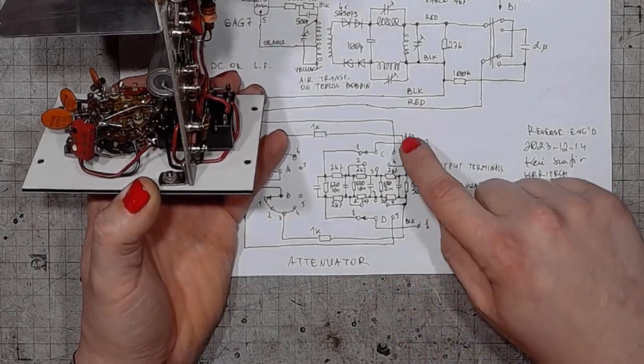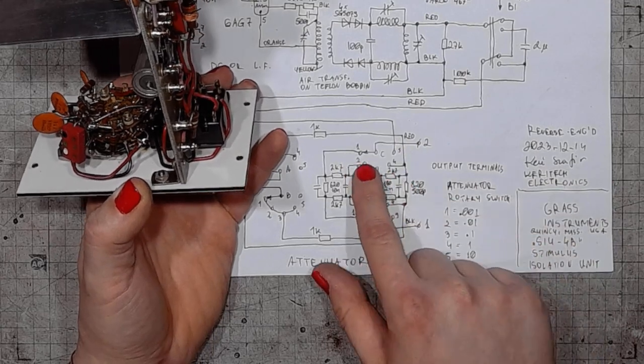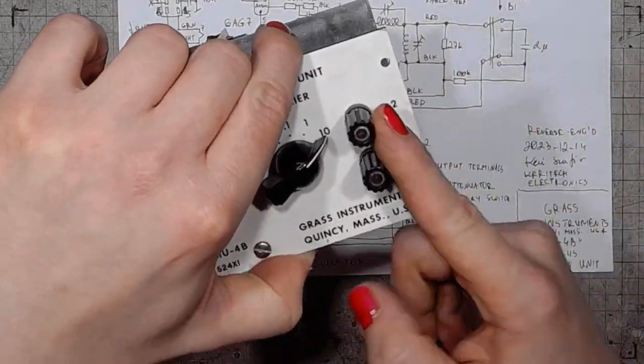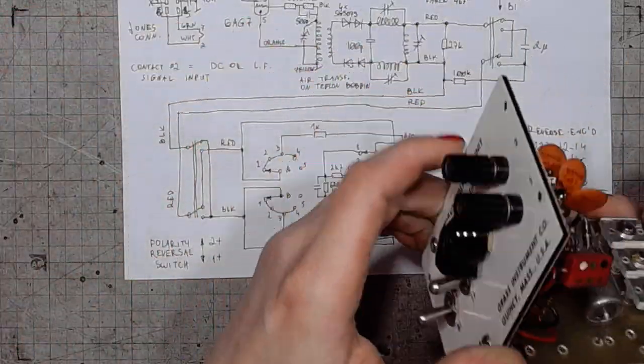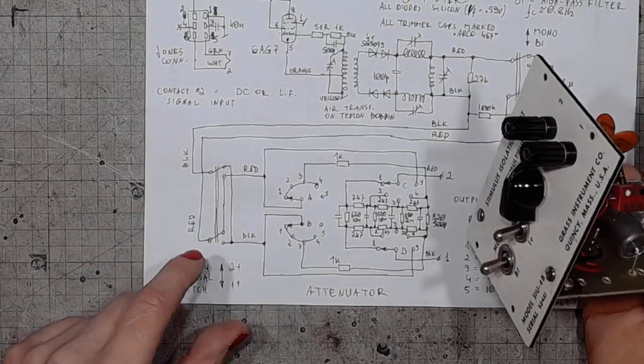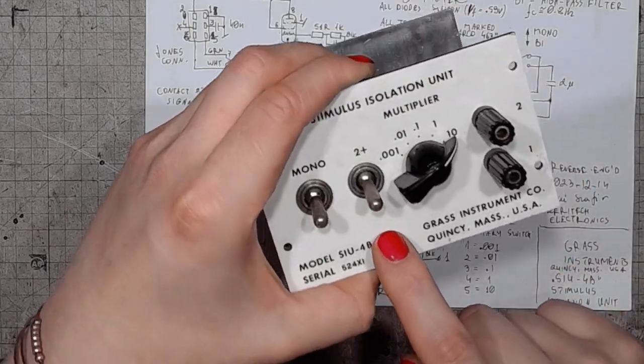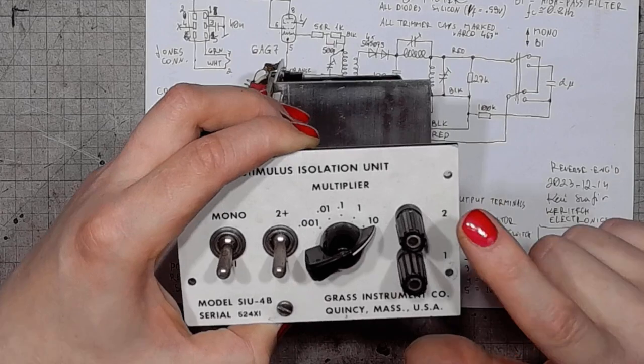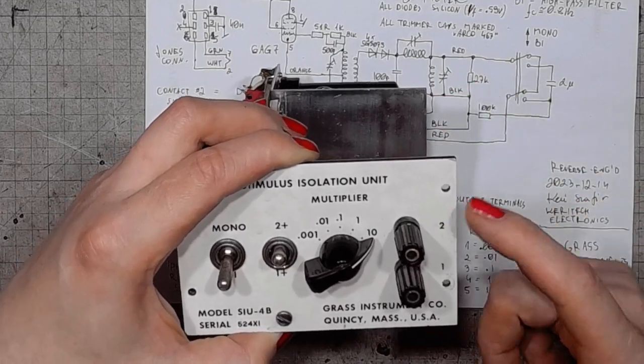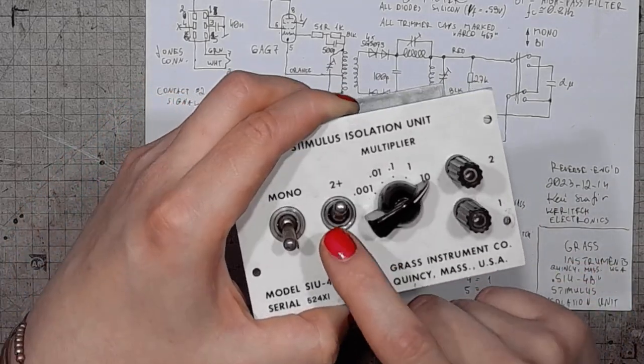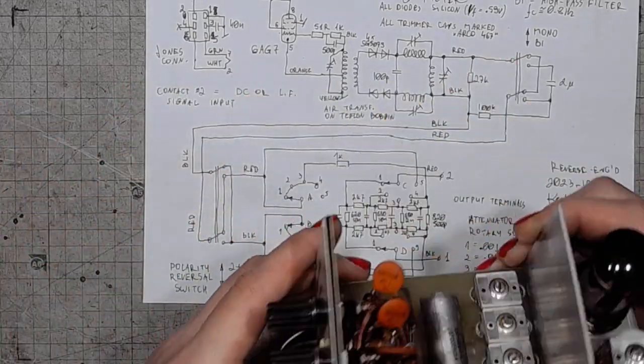Though it will be 5K4 plus whatever is behind this. So it's not all that much of a change. Anyway, going further down those steps on the ladder reduces the output voltage on the terminals. And this switch, it's basically a polarity reversal switch. The marking means that 2+ is the higher potential will be at terminal 2. 1+ means that the higher potential will be at terminal 1. Basically the phasing version.